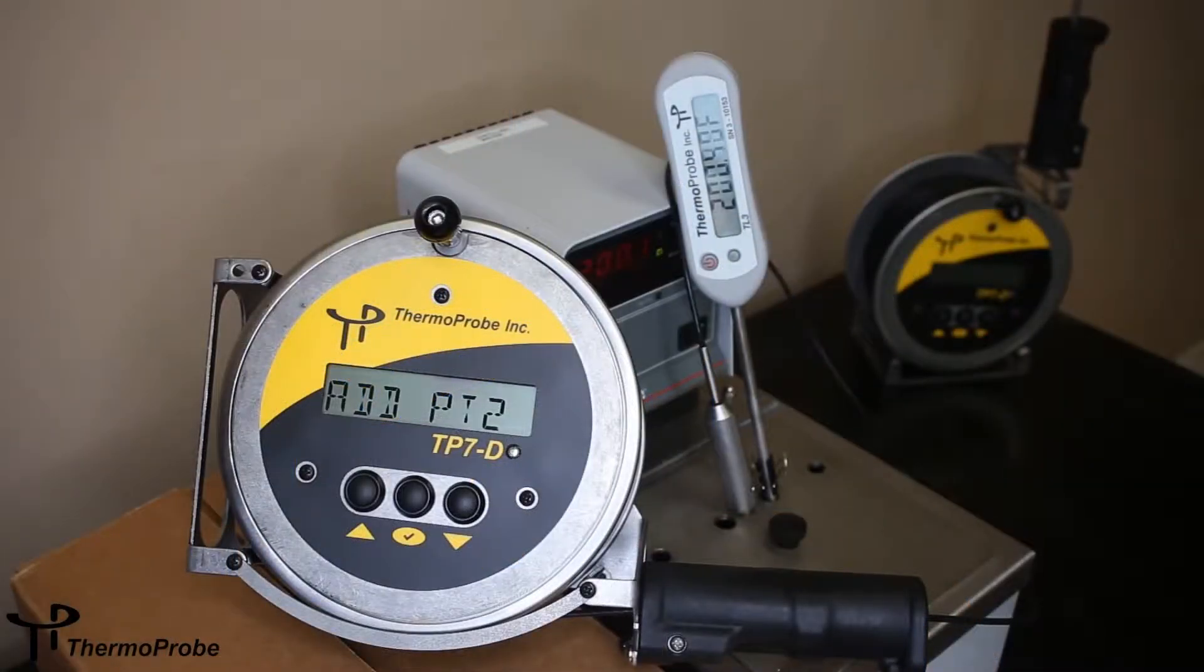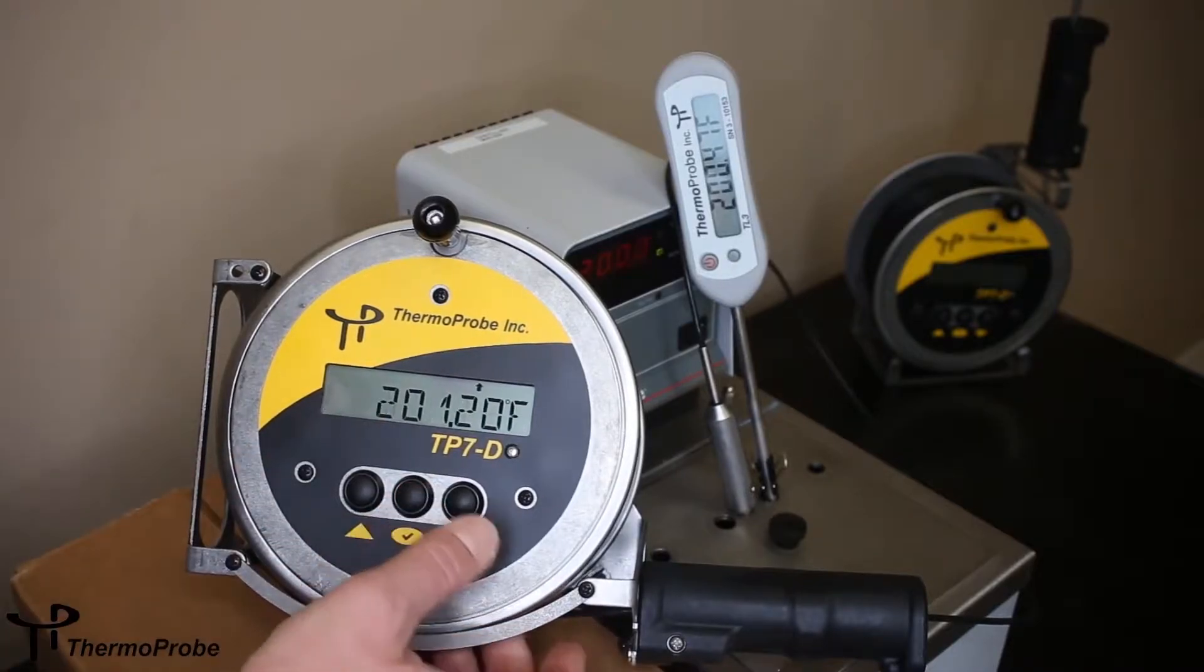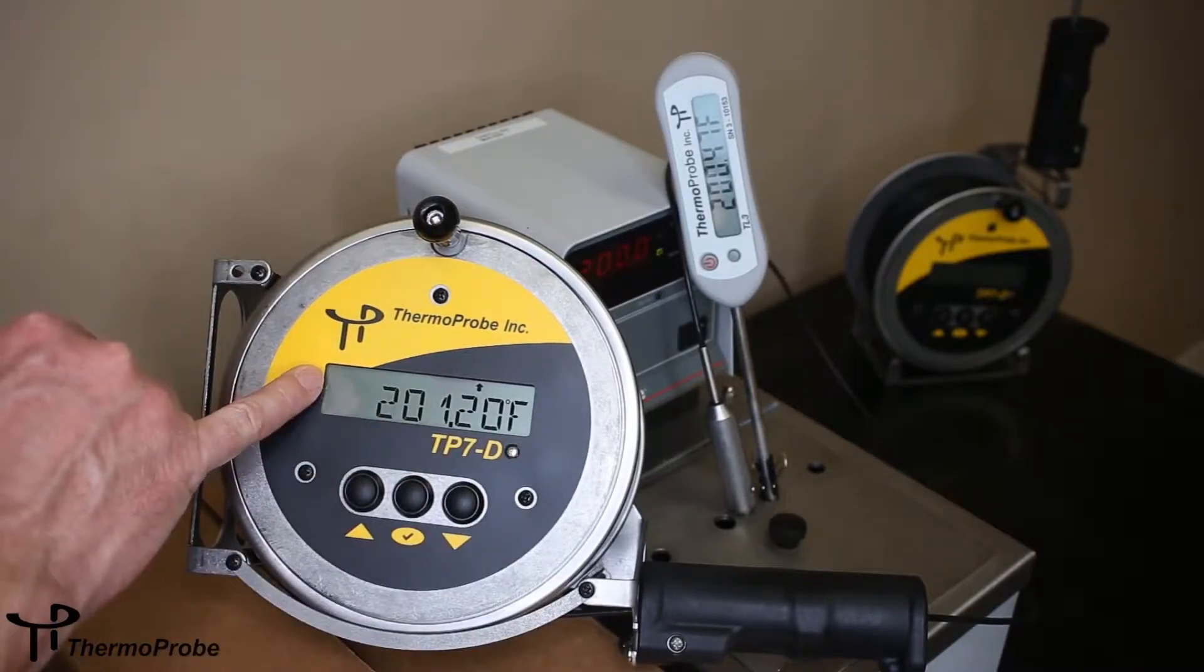To continue the calibration adjustment on the thermoprobe, we moved to a 200 degree Fahrenheit bath. You can do the same using a boiling pot of water. Again, we used our same reference and moved it over. We're showing add point two. We want to hit select, and now we're showing calibration of point two.